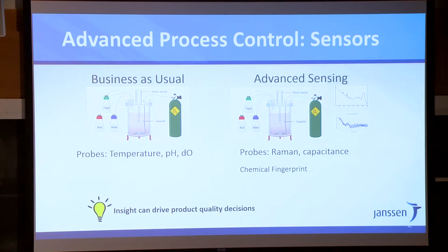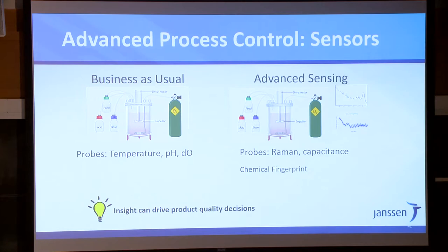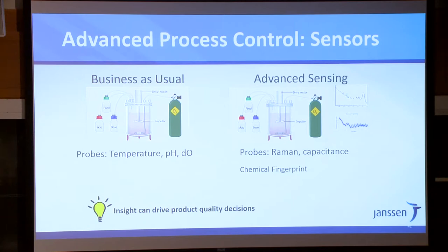Sensors become very important. We start moving away from the black box treatment of the bioreactor. Traditionally, we check temperature, pH, dissolved oxygen, CO2 maybe, and adjust the shear with the agitator speed. But now, when we bring Raman and capacitance probes — which give you the relaxation of the cells — you start getting a digital fingerprint for the process that just takes you in a totally new direction. Then you can combine these with the multivariate analytics.